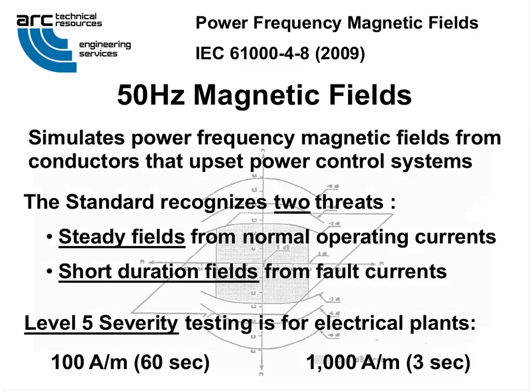In this case, 60 hertz magnetic field. The document can be used for 50 or 60 hertz. Here we would use it at 60. Magnetic field testing simulates power frequency mag fields from nearby conductors or transformers that can upset power control systems. There are two threats we're trying to recognize here: steady fields from normal operating currents and short duration, much higher fields from fault currents. For inside the substation fence, level 5 severity has been called.